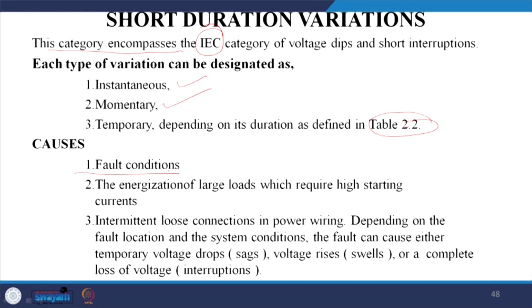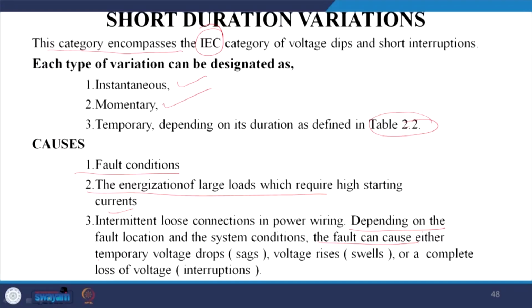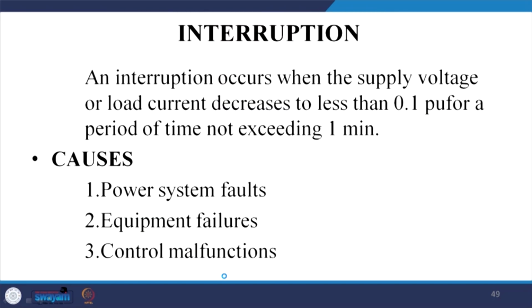Fault conditions can be the cause of these power changes. The energization of a large load which requires high starting current may also cause a temporary interruption, as can intermittent loose connections in the power wiring. Depending on the fault location and the system condition, the fault can cause either temporary voltage drops, for example sag, voltage rise, for example swell, or a complete loss of voltage, that is, interruption. So, what is an interruption? An interruption occurs when the power supply voltage or the load current decreases to less than 0.1 pu for a period of time not exceeding 1 minute.